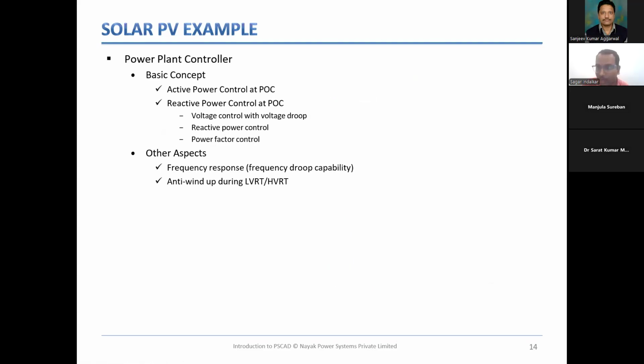Now comes your power plant controller, PPC. The main task of a PPC is to perform active power and reactive power control at your POC or POI. Active power control is your P control, and inside active power control, it has to perform one more function that is called frequency response. It's called frequency response because the grid code asks the renewable energy developers that their plant should provide grid support during system disturbances, for example, change in frequency. So if the frequency deviates from your rated frequency, 50 hertz, beyond a certain deadband, the plant should take some action.